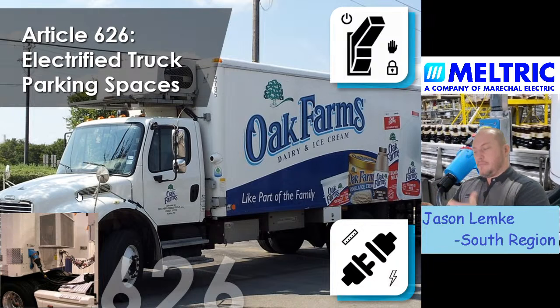So if you've got plugs and receptacles and you're not going upstream and verifying that you're de-energized and following all your electrical safe work procedures while doing that, and you're using the plug-in receptacle to make and break a load, you are actually violating the requirements that your manufacturer is telling you. So when you get your plug-in receptacle, you're going to have some things that are listed for what your device can do. This is true for all equipment. So the device can be a plug-in receptacle. In our case, the device can be a switch.